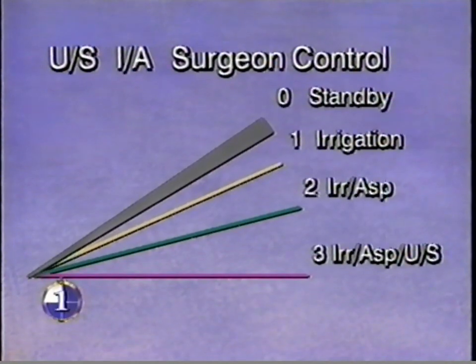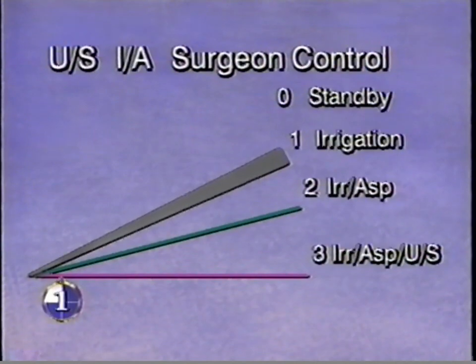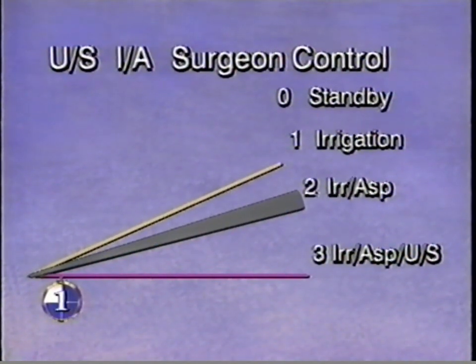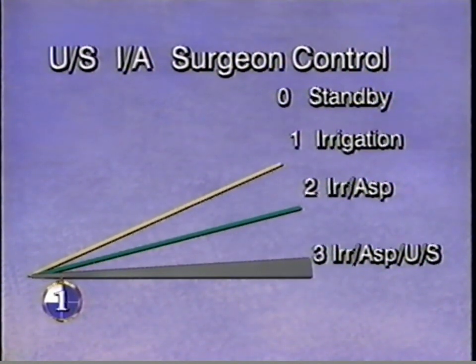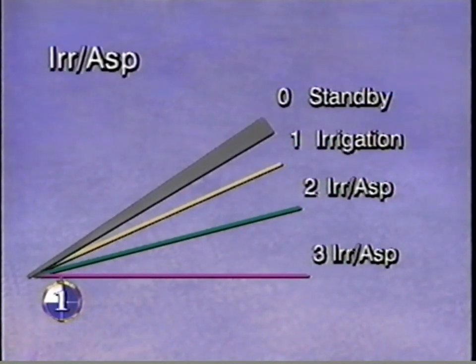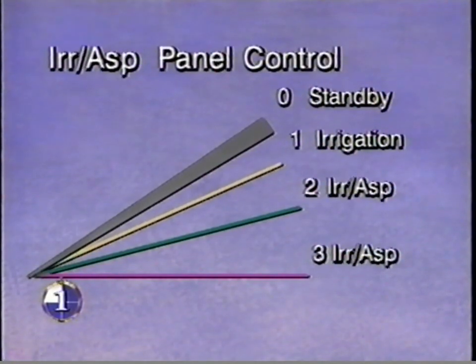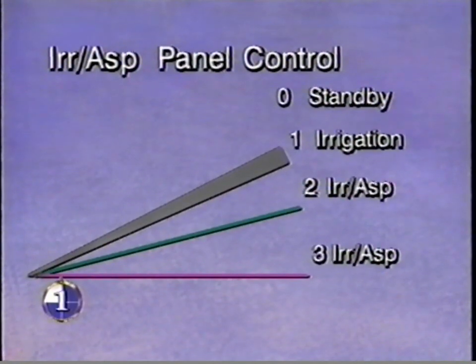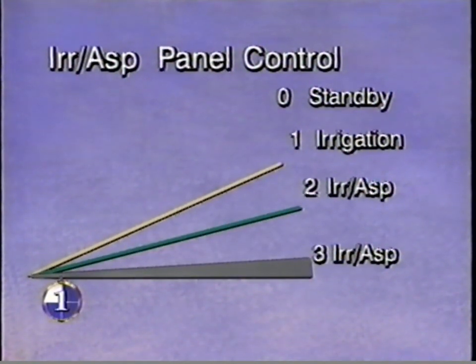Under surgeon control of the US IA submode, position 1 is irrigation. Position 2 is irrigation with linear aspiration. Position 3 is irrigation with linear aspiration and fixed ultrasonics. In the irrigation aspiration mode, panel and surgeon control also differ. Under panel control of all IA submodes, position 1 is irrigation. Positions 2 and 3 are both for irrigation and fixed aspiration, determined by presets on the front screen.